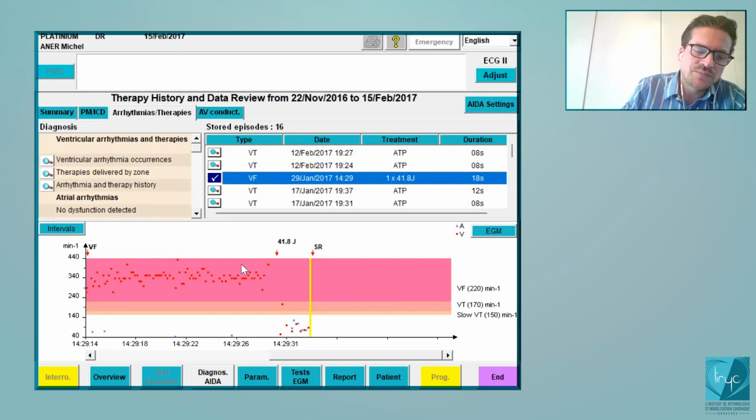First of all, the battery, the capacitors needs to charge. So to deliver a couple of dozens of joules, the ICD has the need to dump the energy from the battery into the capacitors. So this is of course one of the reasons.